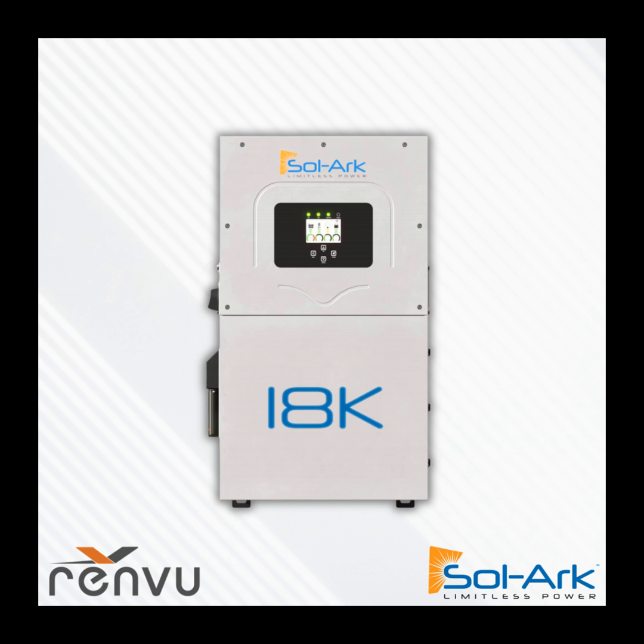Effectively, what I would do for a Sol-Ark commercial system is what most of our installers do: just 1 to 4 inverters, 1 to 4 battery cabinets, and you come in to the load side of the panel and plug in a sub panel, even use that gen port to plug in another sub panel. So selling commercial with a Sol-Ark, you can do a site walk, talk to the facility manager...